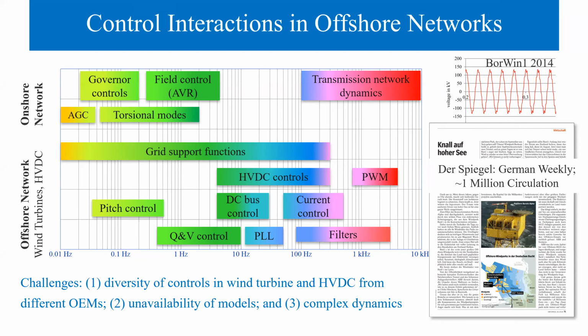One negative experience: we show here the data from the Borwin 1 offshore wind power plant in Germany. They had an incident in 2014 where subsynchronous resonance took place, causing certain hardware issues, giving very bad publicity to this technology. But that issue was addressed by the industry long ago, and this type of operation is now very reliable.